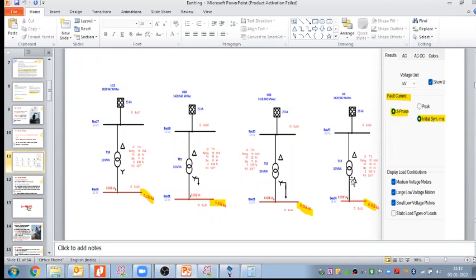Again if I take delta and change the vector configuration of the transformer, the fault current remains the same. So what I understood here is that if I change the vector group or the winding configurations, like solid grounding, NGR grounding, delta, the three phase fault current value will be the same, it is not going to change. It does not depend on the transformer winding and vector group. So what depends on the transformer vector group? The line to ground fault. So the three phase fault current concept is clear, I hope. This is not going to come into the syllabus or the study. This will remain the same.